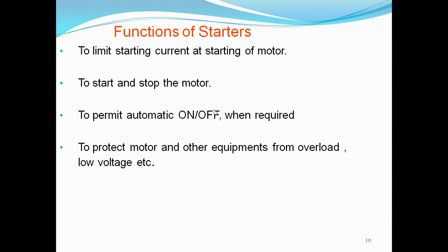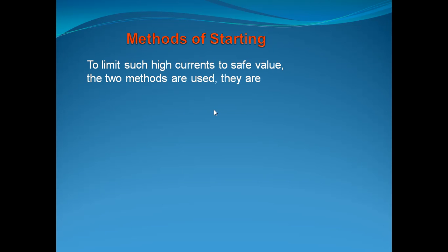So these are the functions of the starter: to limit the starting current, to start and stop the motor, to permit automatic on and off when required, and to protect the motor and other equipment from overload and low voltage.